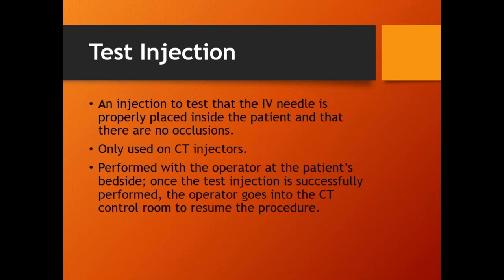For those of you who can see it. Now the first phase was automatically blue, so it's set up to use saline as the test injection. And then there's a flow rate of 1 and a volume of 20. That's excessive for a test injection, but for the example. So you notice there's that first phase, and then right underneath that first phase, there's that white line underneath it. That's indicating a hold. So we'll do the test injection over here.